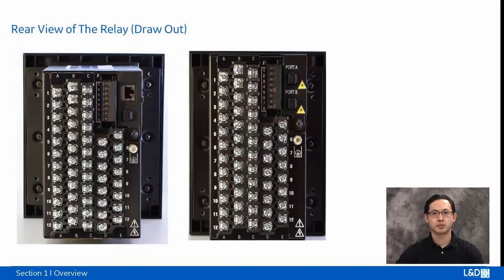Most 3 Series relays have 1 copper and 1 fiber Ethernet port. The order code with 5E will have 2 fiber Ethernet ports. For the draw-out type relay, columns A, B are for output relays. Column C is for digital inputs. Columns D, E are for CT, VT inputs. Column F is for communications, RS485 and IRIG-B inputs.